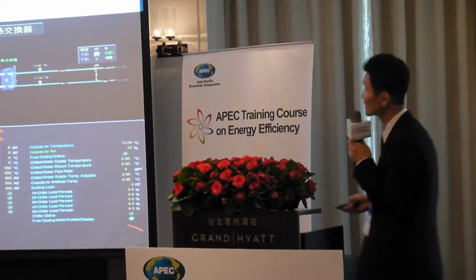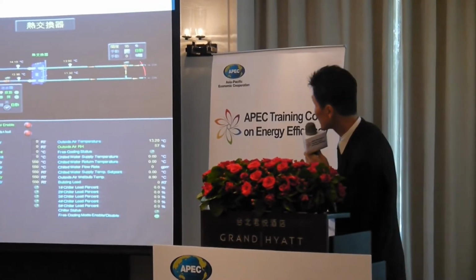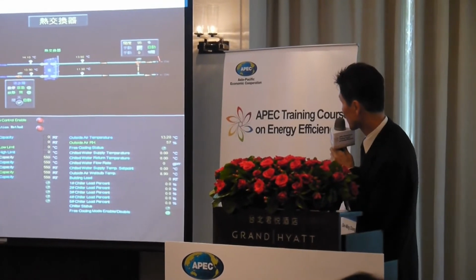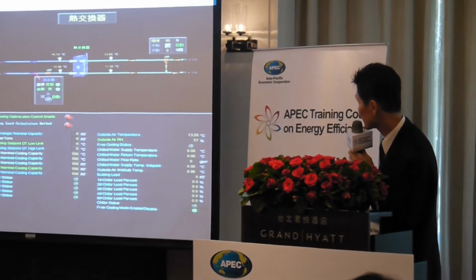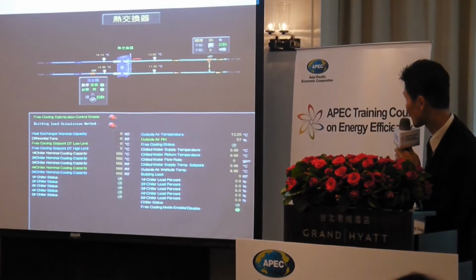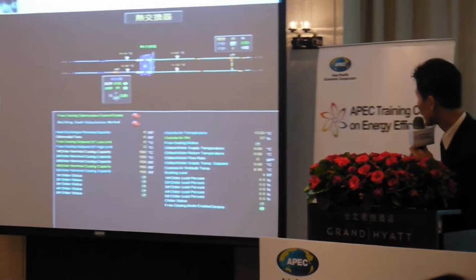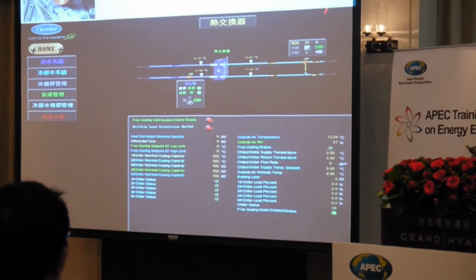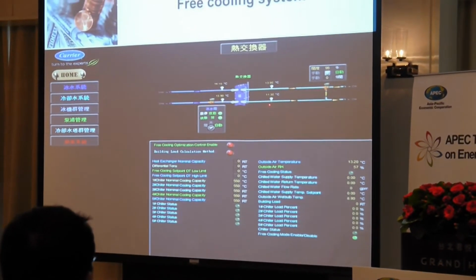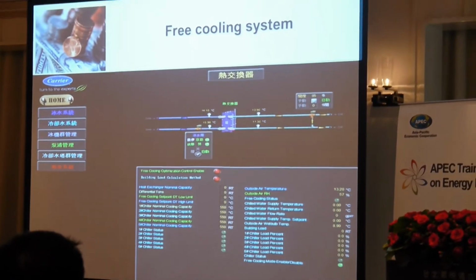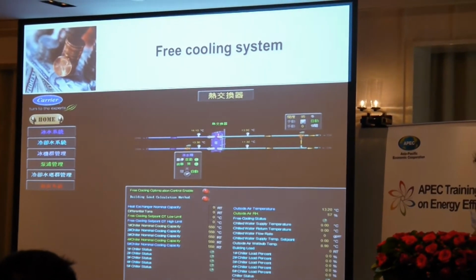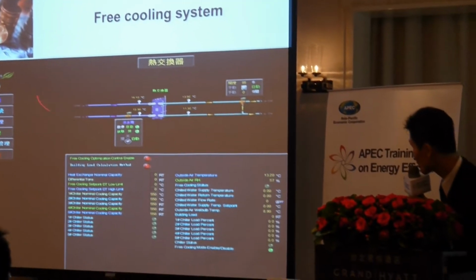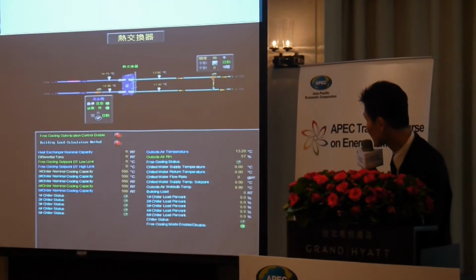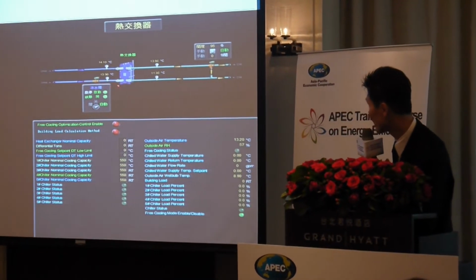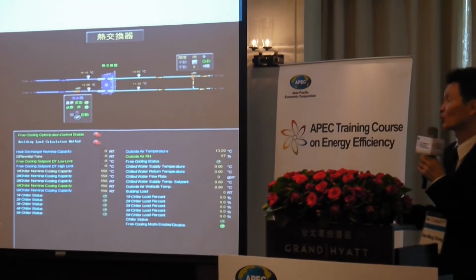And here is the heat exchanger. Here is the condenser pump side, here is the chiller side, and here connects to the cooling tower. Looking at this, coming from the cooling tower it is 11 degrees, and after the heat exchanger it is 13. The chilled water before is 14 and we drop it to 13. And this 13 we supply to our chiller system. So we get the saving.